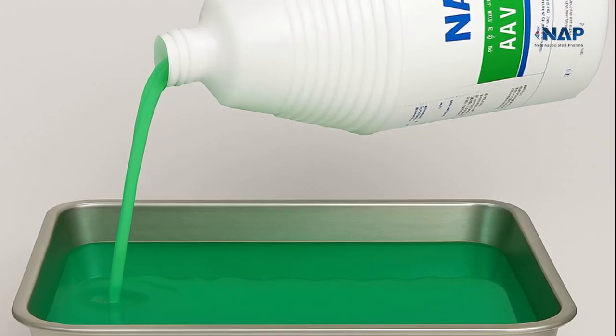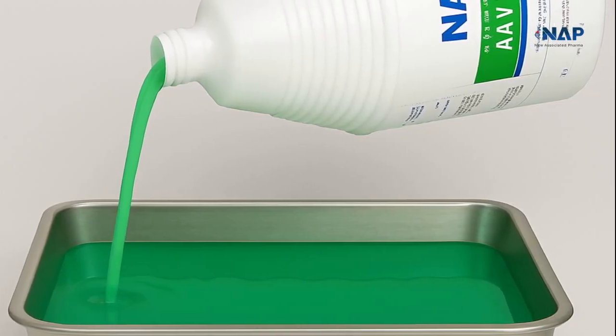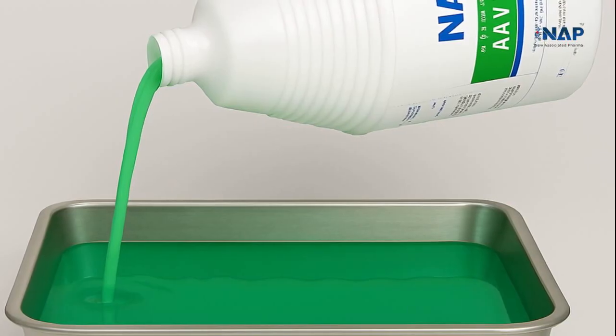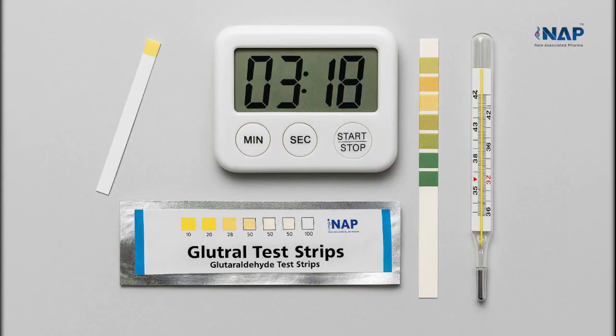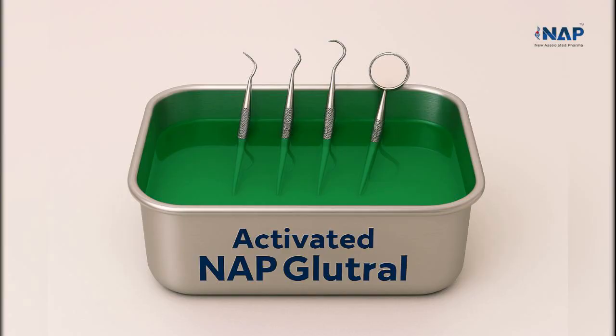Once the instrument is dry, pour activated NAP Glutral solution into a tray without dilution. Before immersing the devices, check the solution's minimum effective concentration, pH, and temperature to ensure optimal conditions. Fully immerse the devices in the activated NAP Glutral solution and allow the contact time to elapse before removing the devices. When removing, use aseptic technique to prevent recontamination.